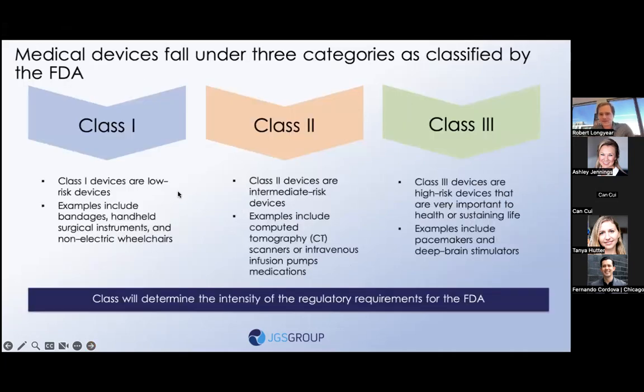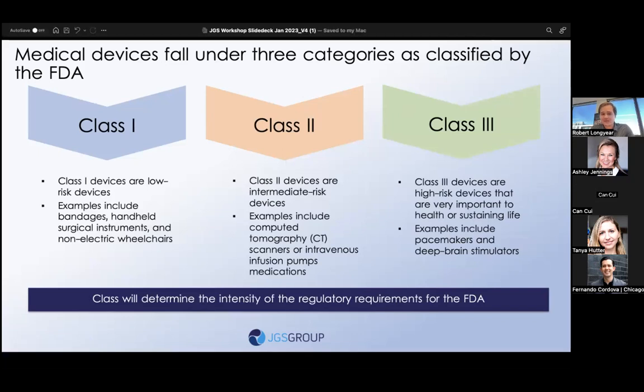The medical devices fall under three categories. You have class one devices, typically low risk devices - bandages, handheld surgical equipment, non-electric wheelchairs. Then you have class two devices, and quite a few of the medical devices we see end up fitting there. It's a little bit less onerous than a class three device, which requires massive sample sizes.